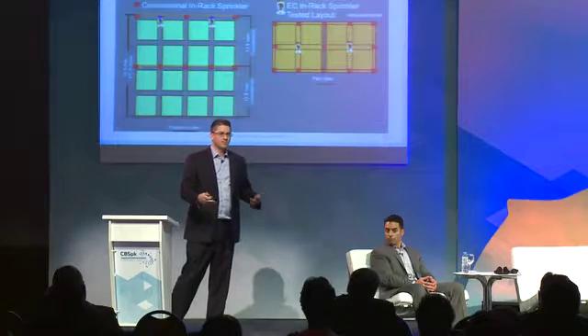The intent is to take a system like the one you saw before that's already in the 2016 edition of NFPA 13 and eliminate about 1 out of every 5 in-rack sprinklers on each level. So for a double row rack, you get rid of the face sprinklers, put the in-rack sprinklers only in the longitudinal flue, and only at essentially every other transverse flue space. You spread them apart.